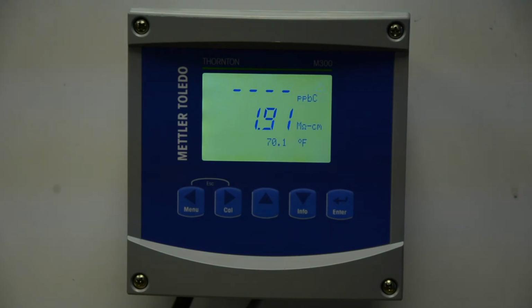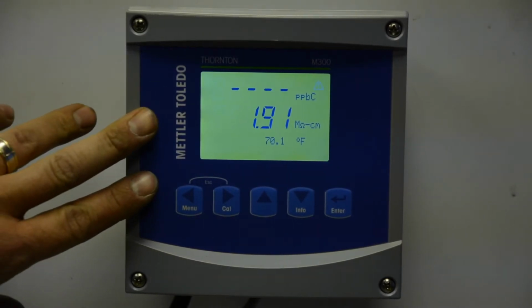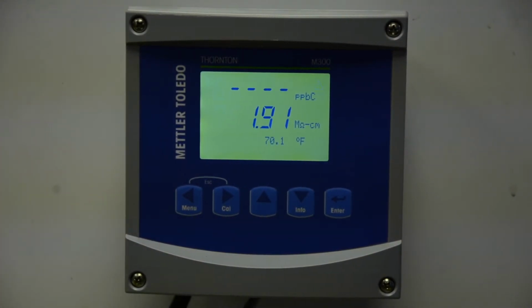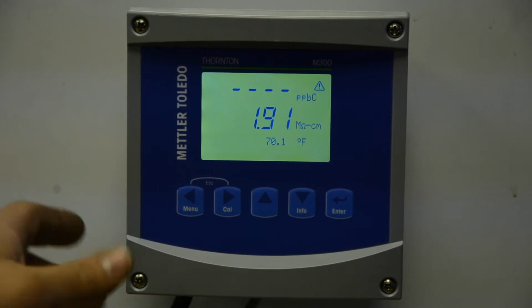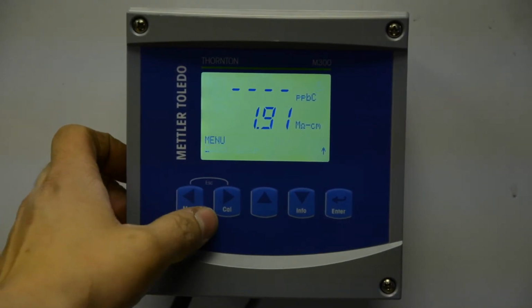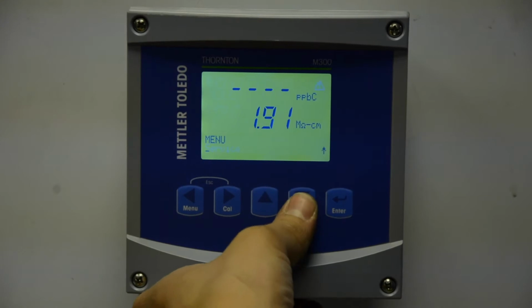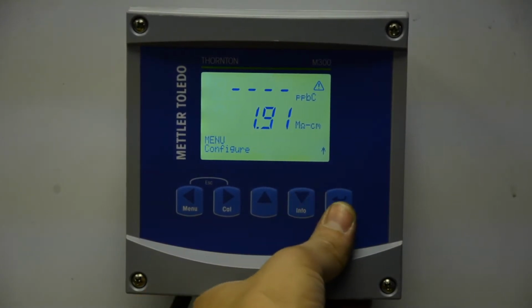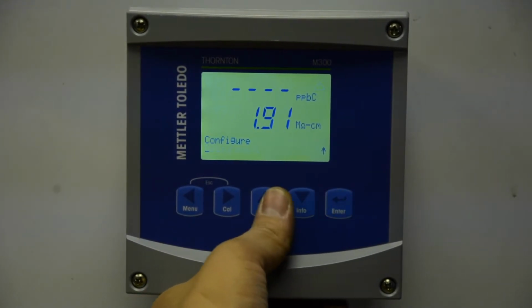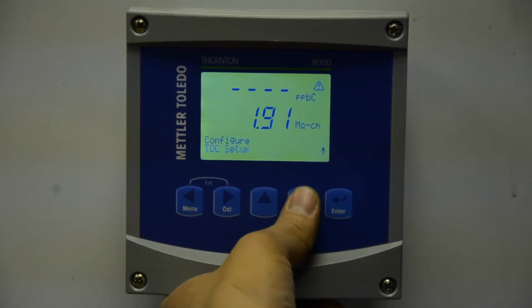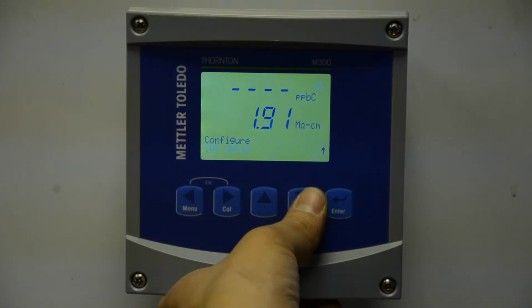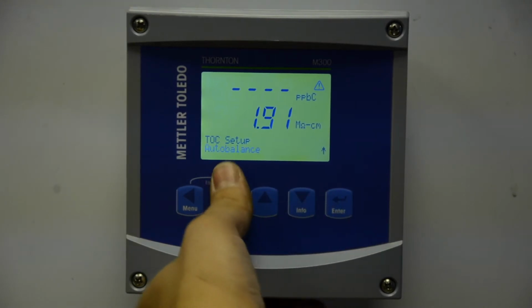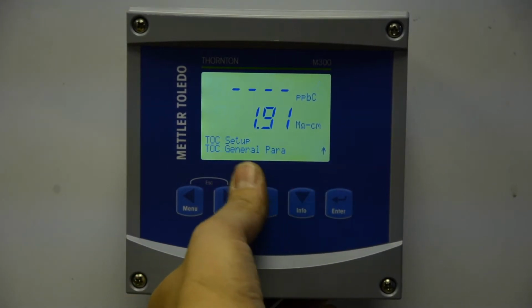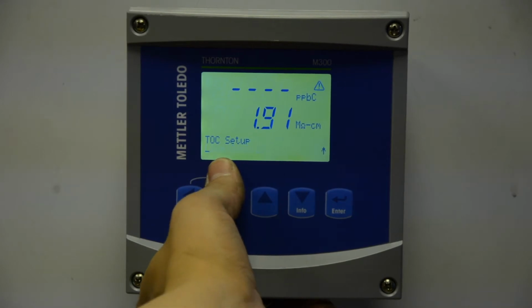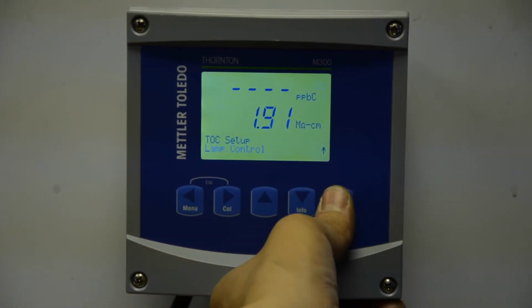Before we start our calibration, we do need to go in and reset the lamp hours on our M300 unit to signify that we replaced a UV lamp. To reset the lamp hours, go into Menu, go to Configure, hit Enter, then go down to TOC Setup, hit Enter. You'll see different choices: Auto Balance, TOC General, and then Lamp Control. Go into Lamp Control, hit Enter.